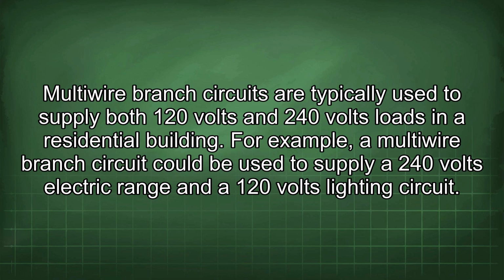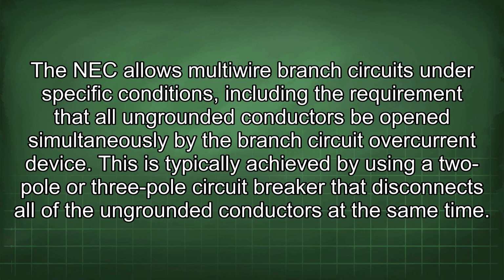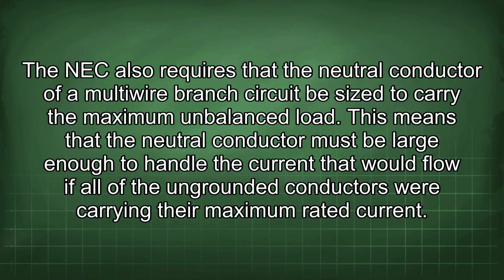120 volts lighting circuit. The NEC allows multi-wire branch circuits under specific conditions, including the requirement that all ungrounded conductors be opened simultaneously by the branch circuit overcurrent device. This is typically achieved by using a 2-pole or 3-pole circuit breaker that disconnects all of the ungrounded conductors at the same time. The NEC also requires that the neutral conductor of a multi-wire branch circuit be sized to carry the maximum unbalanced load. This means that the neutral conductor must be large enough to handle the current that would flow if all of the ungrounded conductors were carrying their maximum rated current.